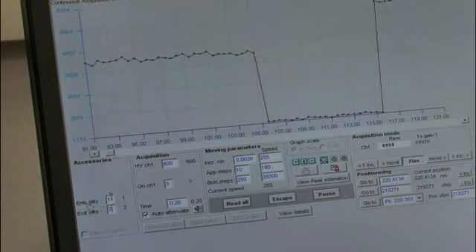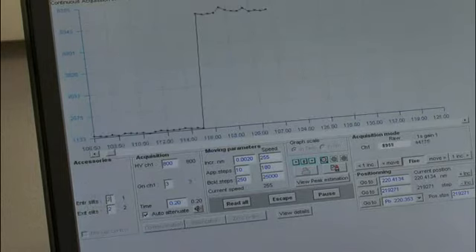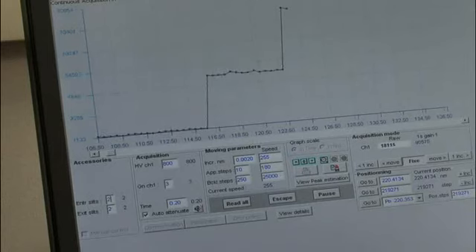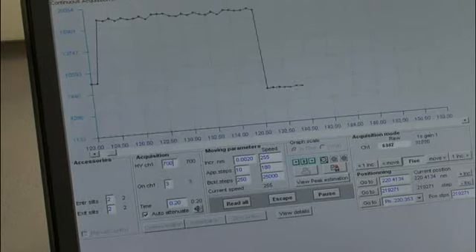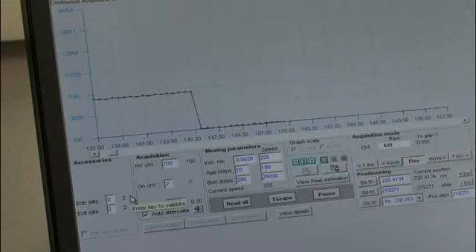And then if I make the entrance slit larger, it should increase it even more. So now I know my slits are working. If I want to reduce my high voltage, I just do this, and it'll reduce the signal. If I want to reduce my gain, this is the gain on the amplifier, that'll reduce it more too. I can increase my acquisition time here, and it'll increase it.